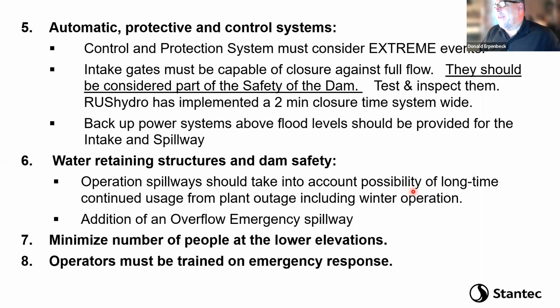Spillway designs need to take into account that the entire plant can go down for long durations. There are design considerations needed for putting the spillway in full-time operational use 24/7 for years on end. One of the things they've done at Sayano is add a massive overflow spillway at the top of the dam that doesn't require gates to get the flow down and around — so they've added a second spillway.